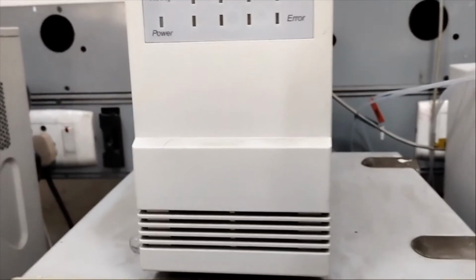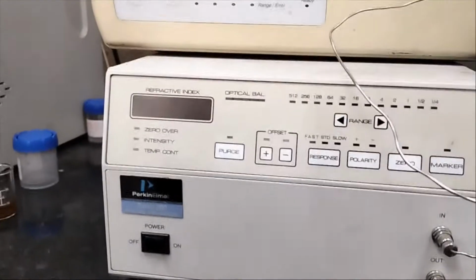Now comes the interface system. The interface system includes chromatography interface and network interface. It would be connecting the software, computer and the instrument together. Now, finally, it moves on to the refractive index detector. From the refractive index detector, the eluent is collected to the waste reservoir by this.